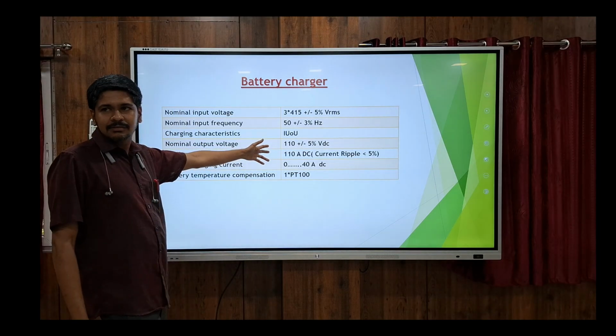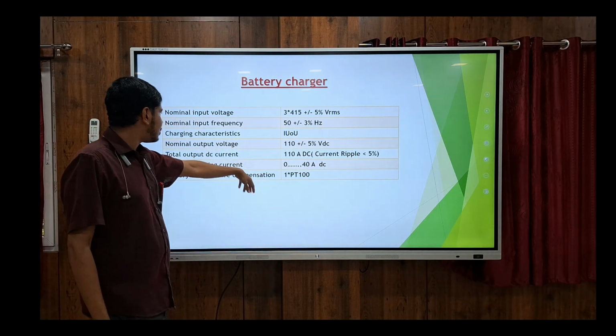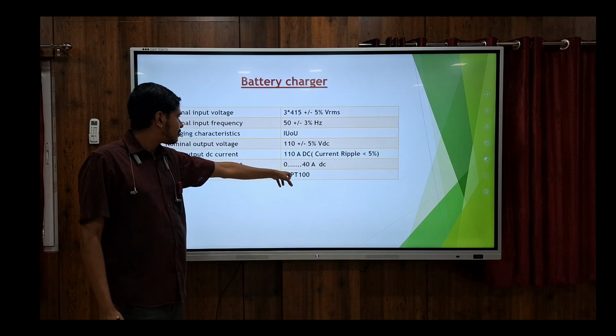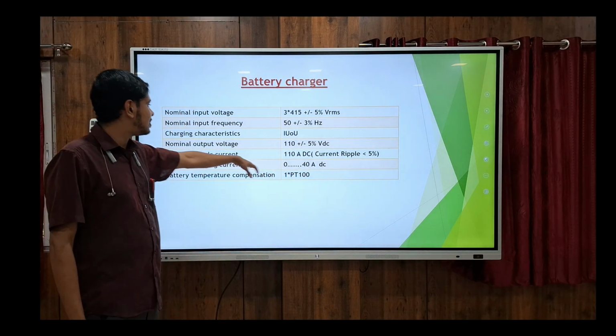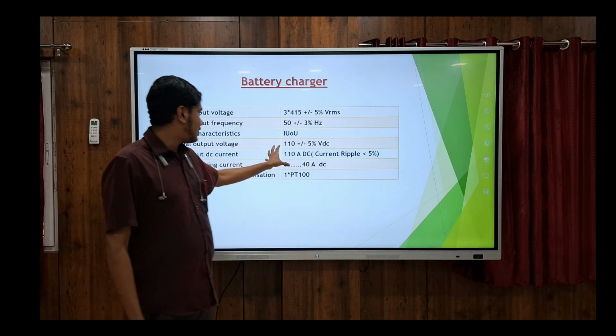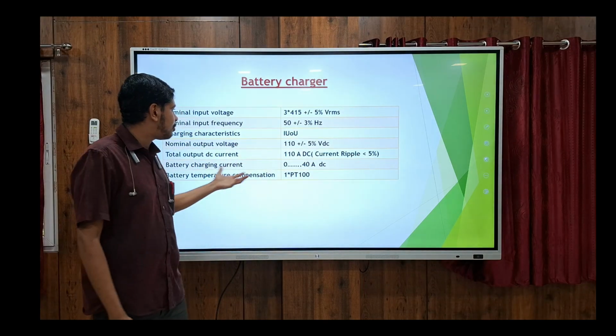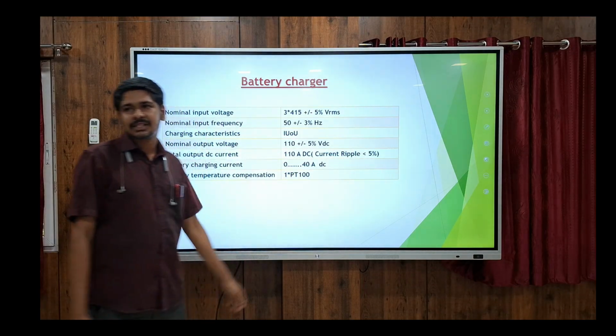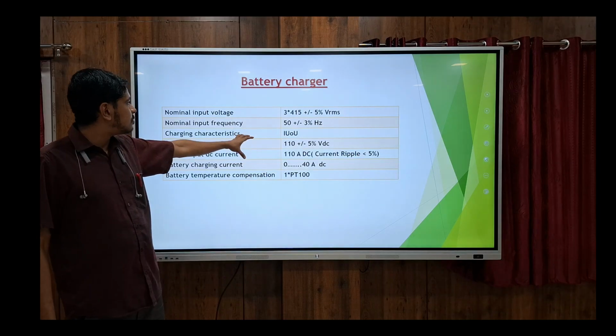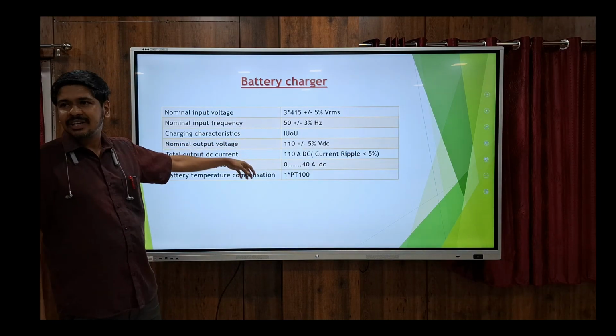Then this is the nominal rating of the battery charger, which I have already told. The temperature sensor is a PT100 sensor, incorporated in this. They are claiming that the output ripple will be less than 5%. The capacity is 110 amps, and the power rating is 12.1 kilowatt.